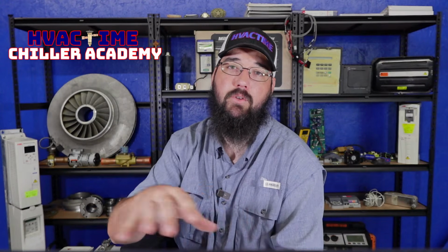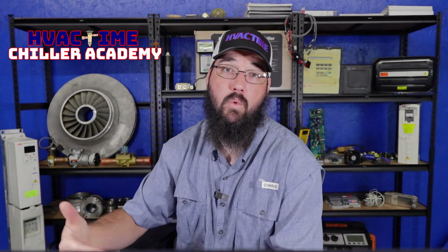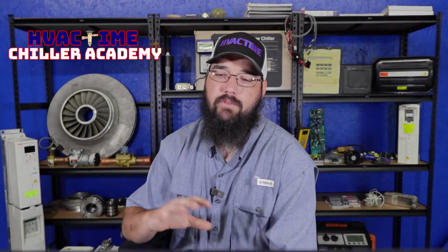That's one of the detriments of going with a small machine or a regular vacuum pump we would use for everyday stuff, is they don't have as much oil volume. So things like the Welch pumps or these industrial pumps from Navac have a much larger oil volume, and the benefit is you get more run time with a wet system before you have to cycle that around. And that's regardless of whether you've got a cold trap involved or anything like that. But one of my complaints with the Welch is they're not as portable as something like this Navac. Why do I prefer this over a Welch? I've had better experience getting this to move around. They've got little dolly carts for it and stuff like that. It's just more portable, and it does an equivalent job in my experience, in my opinion.